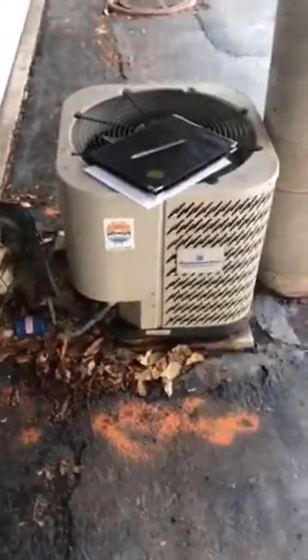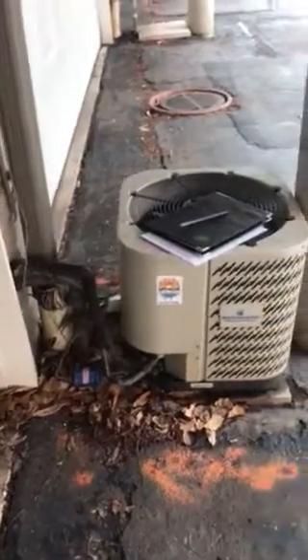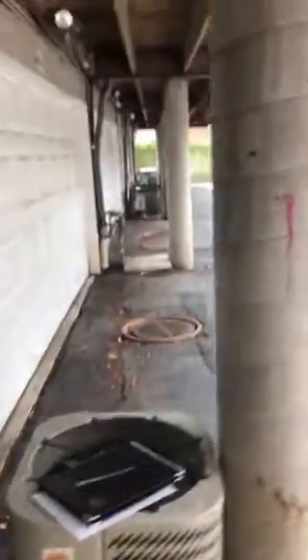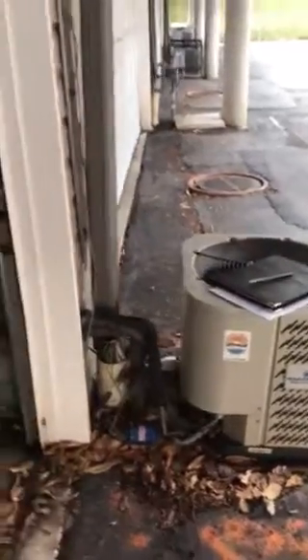We're looking at our condensing unit — right now it's a two-ton unit. From a dimension and physical size standpoint, I'm going to get the exact dimensions of our new unit, because from the edge of this gas pipe here to the edge of this concrete hole right here we've got about 28 inches.